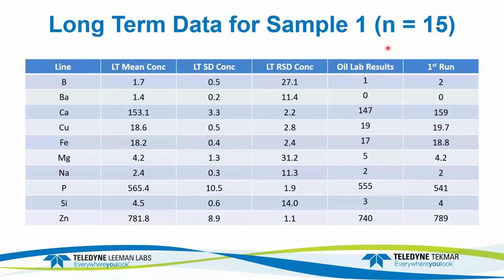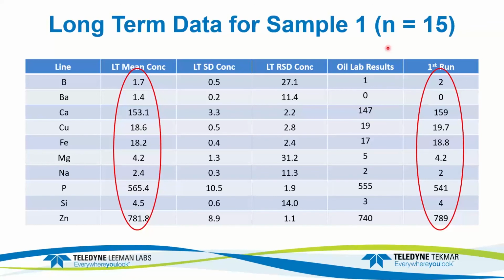Right. Again, long-term data for sample number 1 that we did, there were 10, but we just present this, and this allows us to compare the long-term mean for the data with the ASX Express compared to the long-term mean for the software approach. The time difference between these sets of samples was probably about a month. One was before Christmas and one was after Christmas. So when we got back, the data compare very, very well with the original oil lab results and with the first run where we used just software features to increase the speed. And now we've gone to the maximum speed we can go easily, and we can see that the accuracy and stability compared to the original data is quite good.